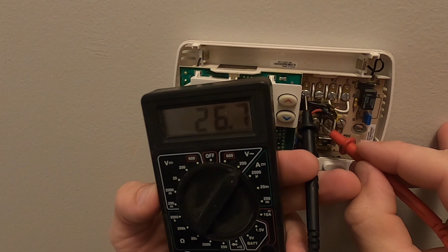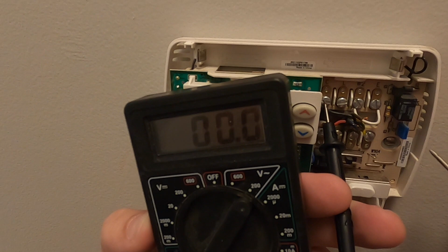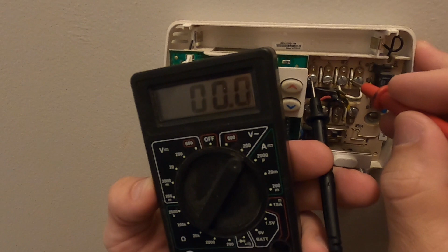And again, this is the reversing valve, and depending on what kind of heat pump you have, you're either going to have voltage or not, depending on whether heating or cooling. You have to look that up. But at this point, we know that's not the problem, because we're getting cool. The line coming in is cool, not hot, to the coil downstairs. So I know it's not accidentally heating instead of cooling, but it is bringing on the emergency heat, backup heat.